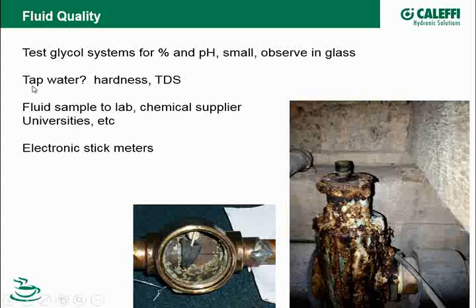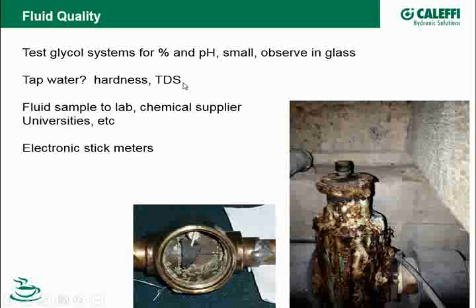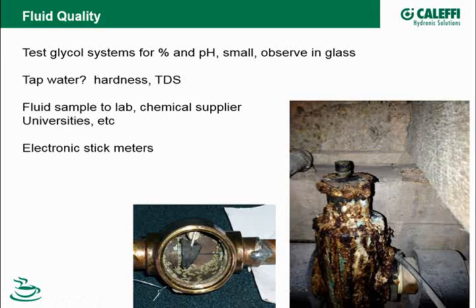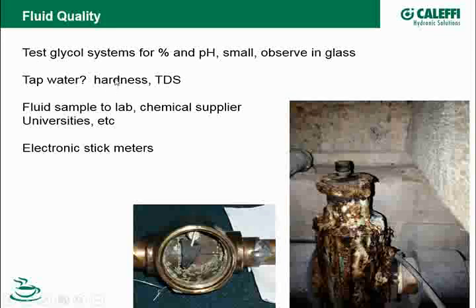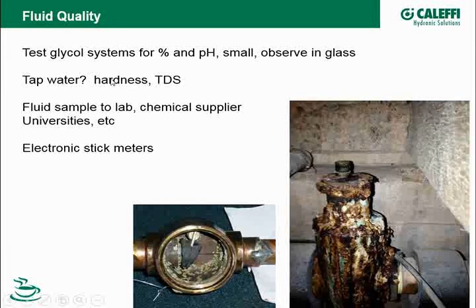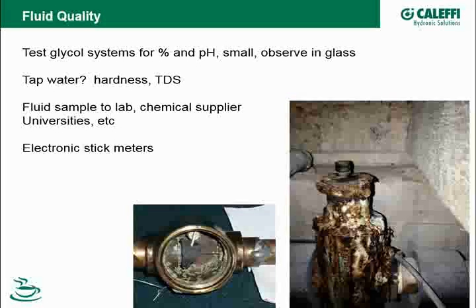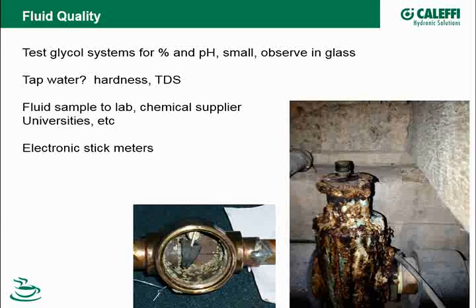Now, basic tap water. A lot of the jobs that you fill with the water that's available on the job, if it's city water from a city system or from a well system, probably hardness is one of the biggest numbers that you want to know there. TDS, total dissolved solids, there are little stick meters I'll show you that you can buy for that, not very expensive. I would check that if you're doing a new job, filling it up for the first time, and see how hard the water is. And this is a very inexpensive, simple test kit for checking the hardness. And I would say if it's over about 12 grains hard, I would consider either bringing some water in from another source that's a better quality water, or maybe getting a little deionized machine that you can put on the fill water and just fill through that to make sure that you've scrubbed some of that hardness out.